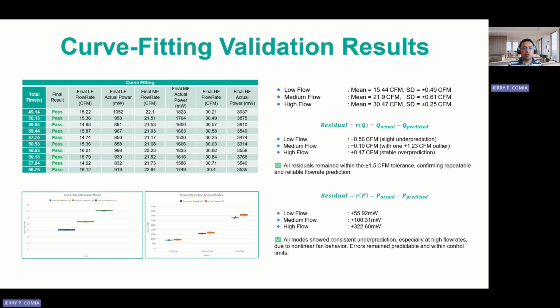The slide presents the validation results of the curve fitting method. Across the 10 trials, all curve fitting tests passed. The low flow mean was 15.44 CFM, the medium mean was 21.9 CFM, and the high flow mean was 30.47 CFM. The residual equation is residual equals actual value minus predicted value.